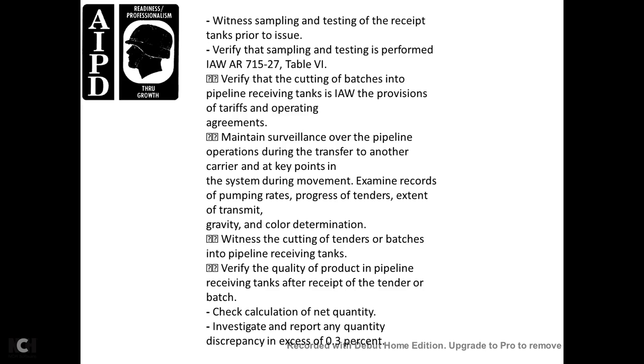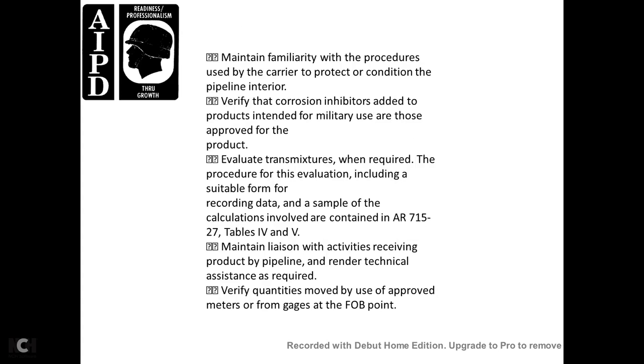For FOB destination deliveries, witness sampling and testing of receipt tanks prior to use per AR-715-27, Table 6. Verify cutting of batches in pipelines receiving tanks per tariff and operating agreements. Maintain surveillance over pipeline operations during transfers at key points in the system. Examine records of pump rates and progress, tender gravity and color determination. Witness cutting of tenders and batches in pipeline receiving tanks. Verify product quality in the pipeline receiving tank after receiving the tender batch, and check calculations of net quantity. Investigate and report any quantity discrepancy in excess of 0.3 percent.